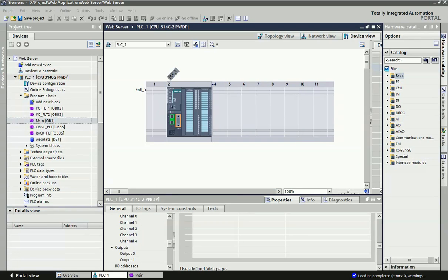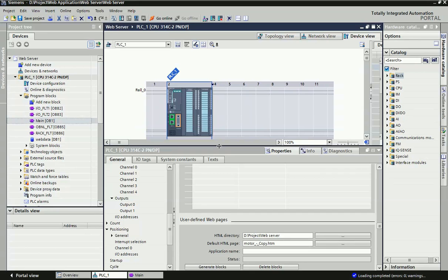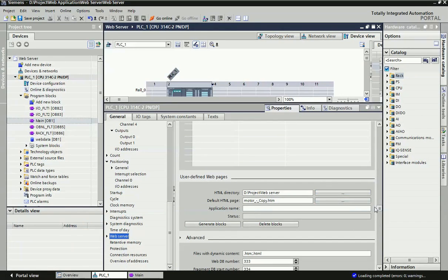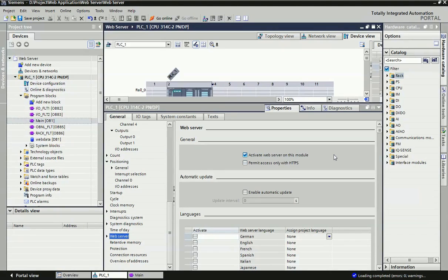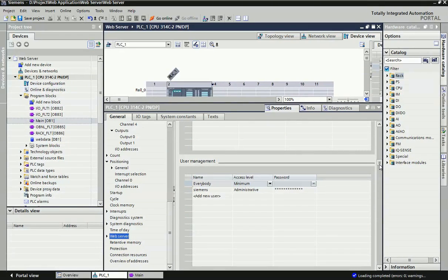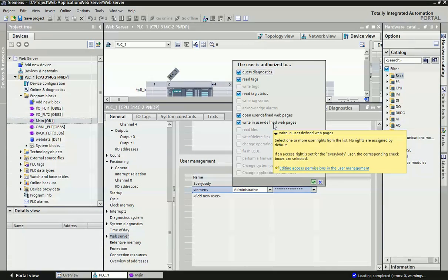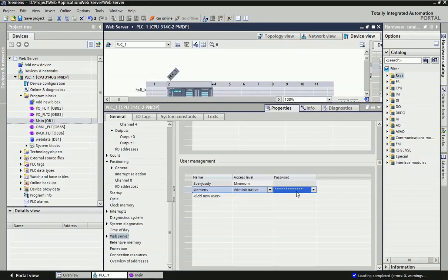Now we will start how we can configure this web server in Siemens TIA Portal with the S7-300 kit. First, go to the properties of the module and you will find the web server option on the downside. In the web server settings, you need to first activate the web server on this module. Then go to user management where you can define different usernames and access levels. Here I have created one username 'Siemens' and provided full access. You can also set a password for authorization.